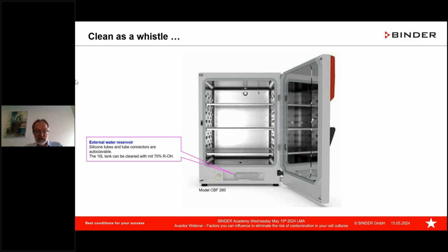Then, as already shown and mentioned, how to exchange that external water bath. Here you have that. The tubes, normally you can autoclave, clean with 70% alcohol. That is easy. If you have a tank feeding multiple CO2 incubators, that is also possible to disinfect with 70% alcohol. The exterior water bath can be accessible from front, like here, or it can be positioned on the right or left hand side of the unit, mounted in the housing where you can refill it over specific connections. So that's also something to consider, regular exchange of the container.